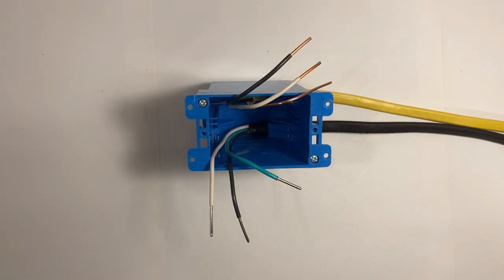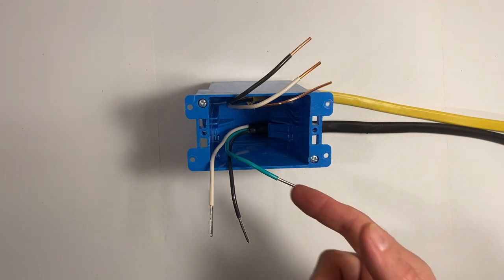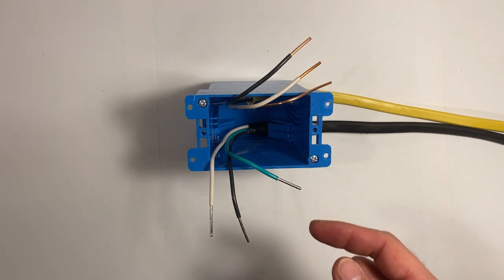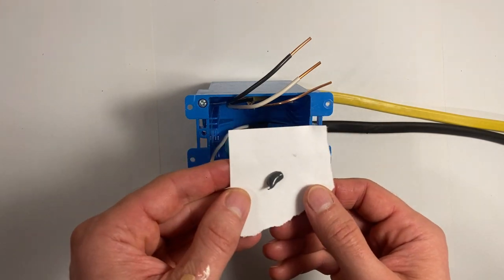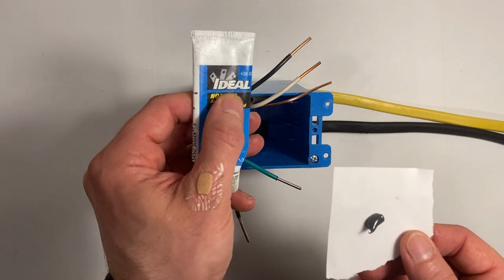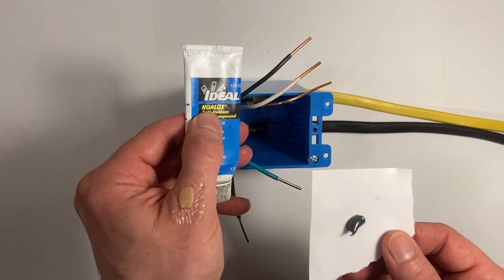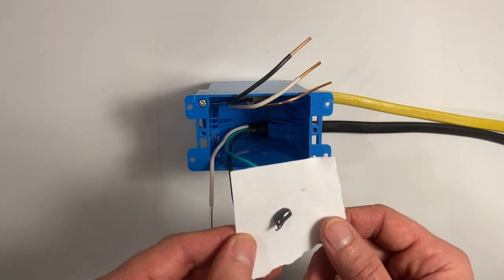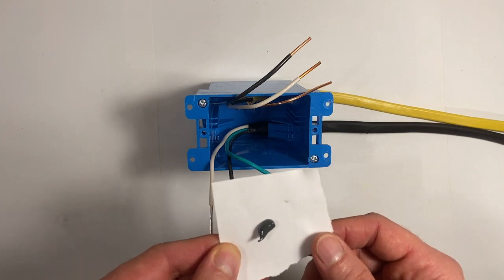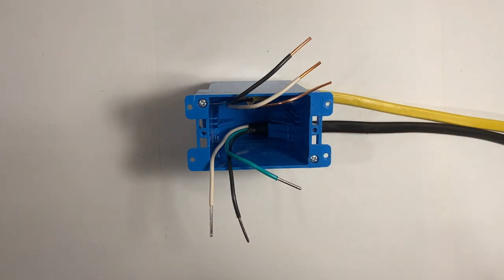As I mentioned in the theory part, one of the parts to the solid aluminum solution is find a way to fight oxidation, that thin invisible or white film of oxide on the surface of aluminum that makes the electrical contact not so good. There are pastes that can fight that. This one is called Noalox, no aluminum oxidation hence the name. It's supposed to cut through the existing coat of oxide and prevent more oxides from forming. However, many of the existing products on the market already come pre-loaded with this paste.